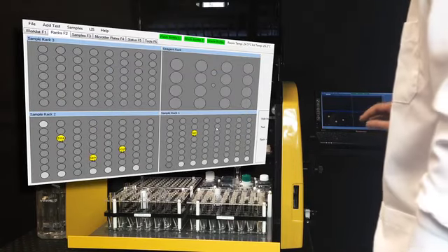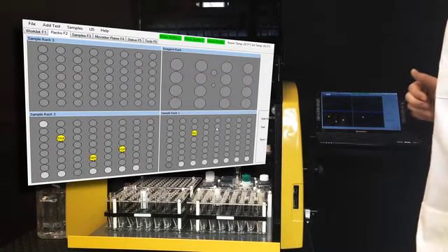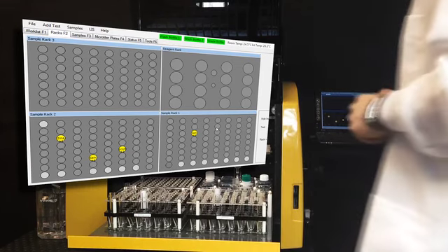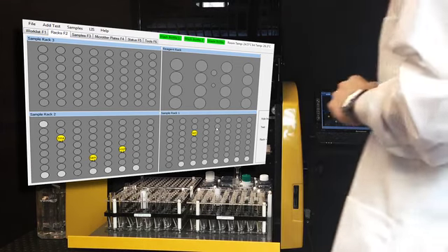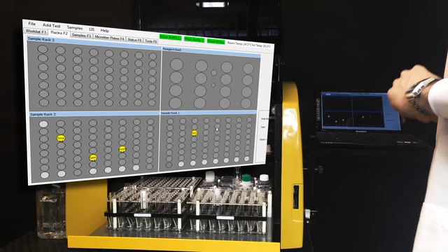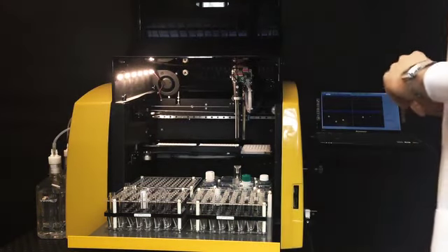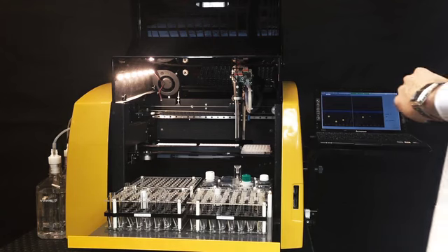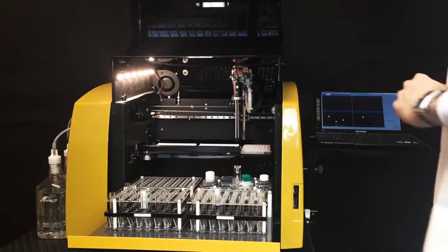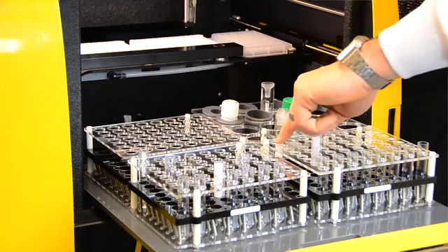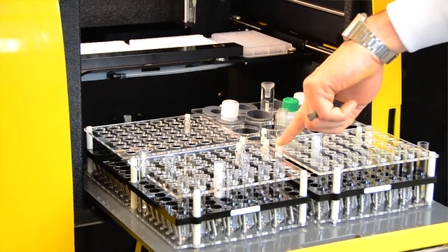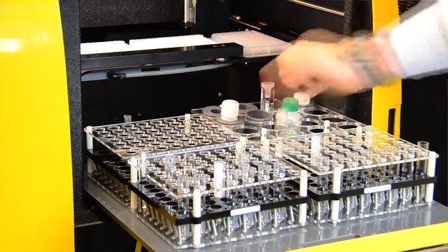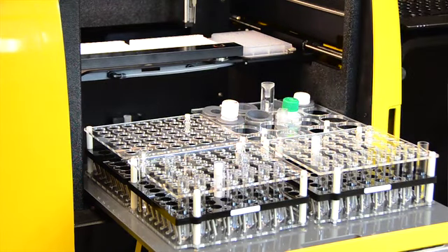Okay, we'll click finished. And as you see, the locations of the samples that you just placed, both using manual entry and barcode scanning, are in the sample racks exactly where you placed them. They do not have to be in any specific order. Now, if you don't care to use the intelligent rack feature, you can turn that off and simply load them starting from the first location in sample rack 1, then moving to sample rack 2, and then to sample rack 3. The instrument works in both ways.